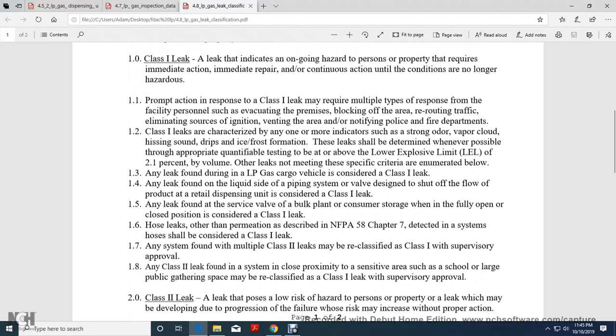Prompt action in response to Class 1 leaks may require multiple types of response from facility personnel, including evacuating premises, blocking off the area, rerouting traffic, eliminating sources of ignition, venting of the area, and notifying police and fire departments.